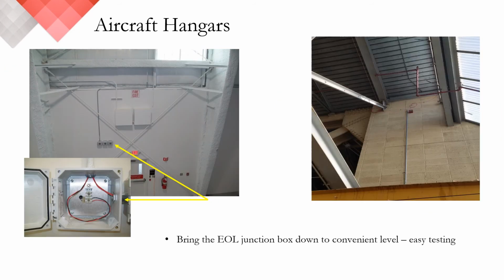As opposed to hundreds, if not thousands of individual detectors, a large facility can be zoned and have the end-of-line resistor brought to a convenient location for testing. What you're seeing here is an image of a regional hangar here in Massachusetts with about 6,000 linear feet of detection broken down into 3 zones. As you can see, all that's required to test this system is a 6-foot ladder and about 15 minutes. We've even included an optional test button to make things even more convenient. In these facilities, false alarms are major issues, and where there are false alarms, discrimination is a huge benefit. Both CTI and fiber optic can provide these features to ensure a worry-free installation.